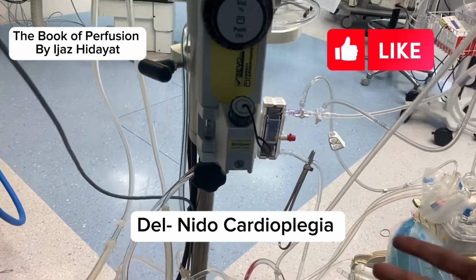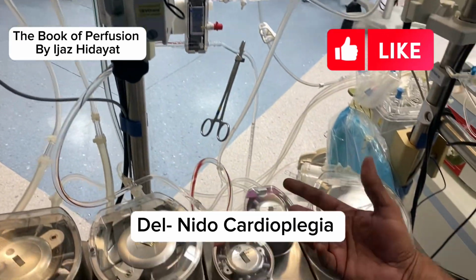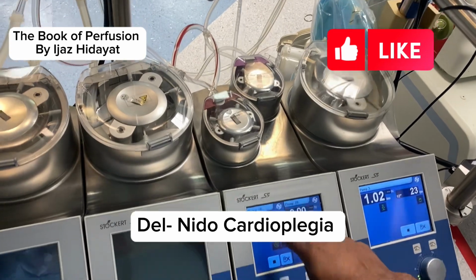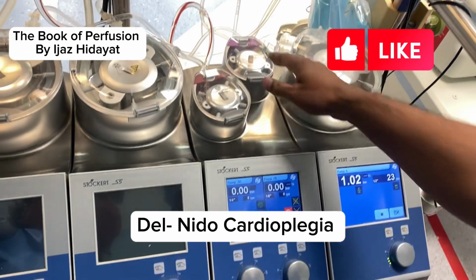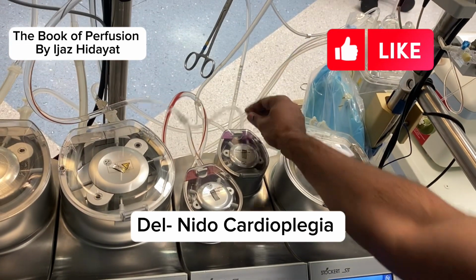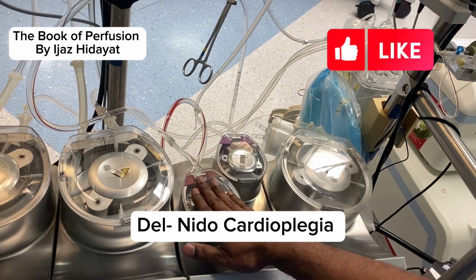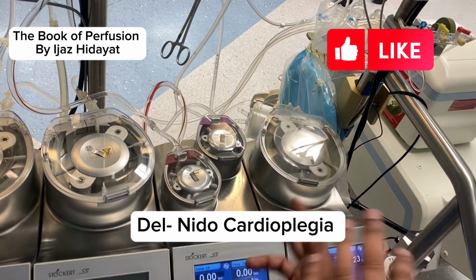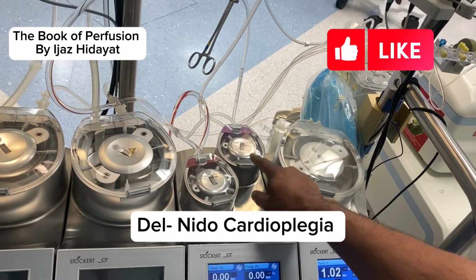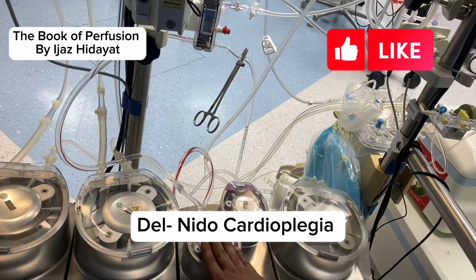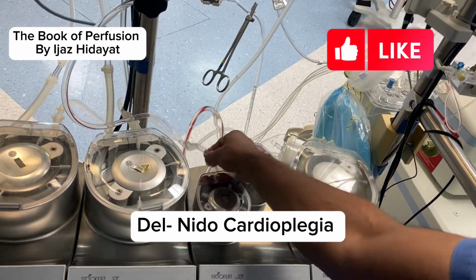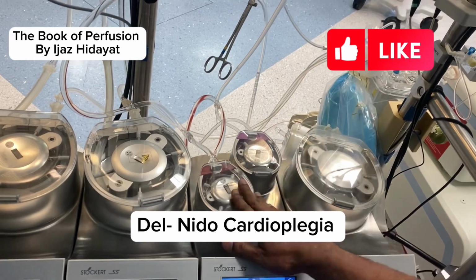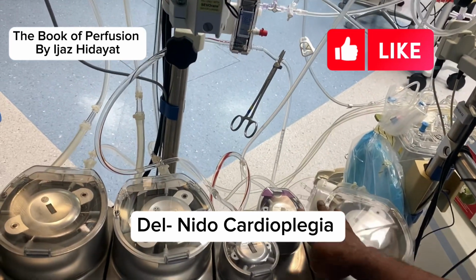But for the Del Nido, we have to do the opposite. This is your main pump, and now it will be reversed. The crystalloid part will come here and the blood will go there. So now we're switching. The crystalloid will become the main pump, and the 1/4 tube coming from the oxygenator will be switched to the slave.